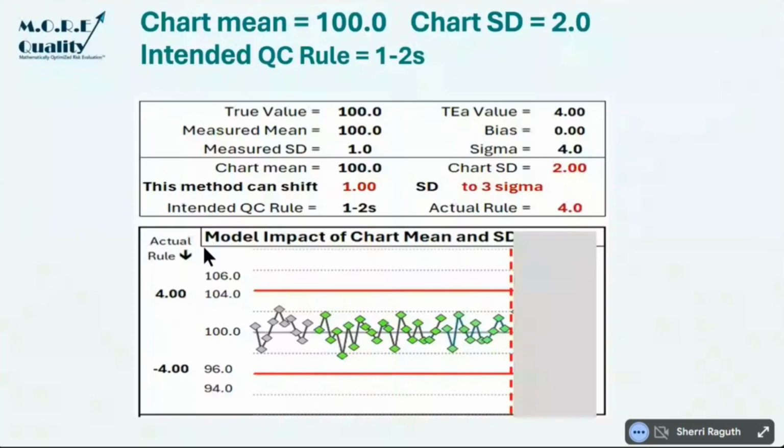All right, I've got a question for you. Sure. Ravimbo is asking: we haven't really used sigmas over this side, so I guess that's where the confusion is. Does it translate to SD on the QC chart? Is 3 sigma plus or minus 3 SD? No, very good question. Sean agrees. Sigma is how far the mean can move until you hit the allowable error limit. Your plus or minus 3 SD on the QC chart is what they call a standard deviation index, and that's how far that result is from the measured mean.